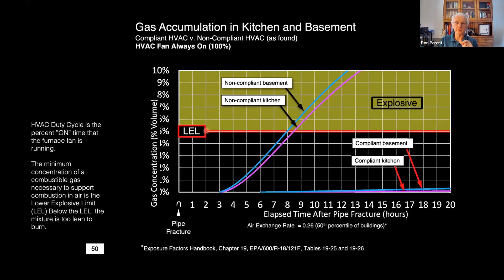The gas concentration in the basement got to be even higher than the concentration in the kitchen. But importantly, if the ductwork is sealed on both ends, according to code, even with the undersized grill, the gas concentration in either the kitchen or the basement never gets up anywhere near the LEL. So the conclusion from that is that we found gas concentrations at the foundation in either case got to be as high as 86%, which is very high. And that the foundation crack formed the pathway for gas to flow into the basement. But the undersized floor grill combined with the open air duct created negative pressure in the basement. The gas concentration in the kitchen exceeded 5% LEL. And a code compliant installation, in spite of those issues, would not have exceeded the LEL, and the incident wouldn't have occurred.